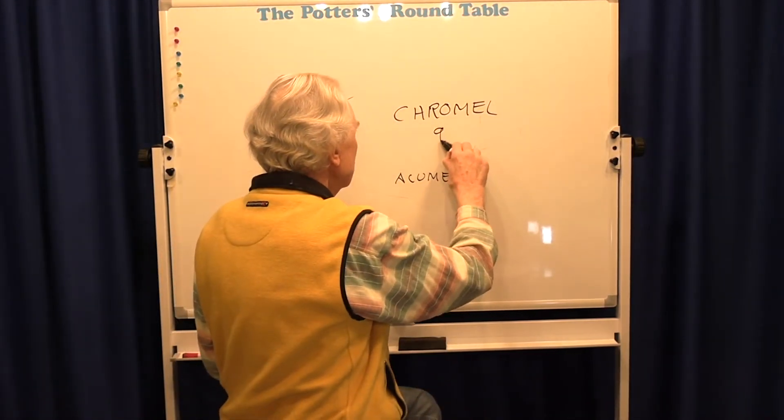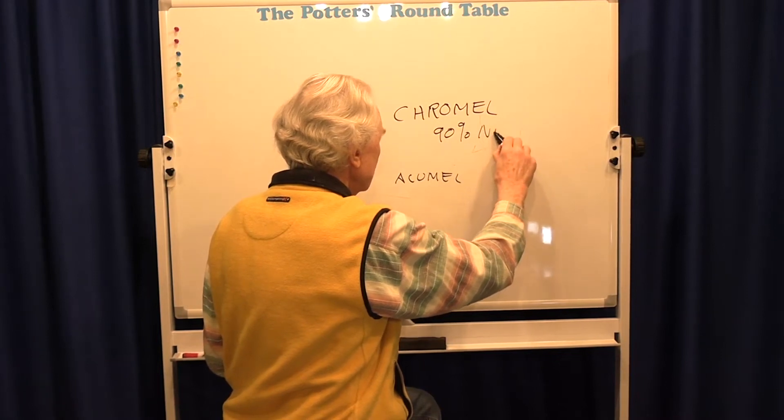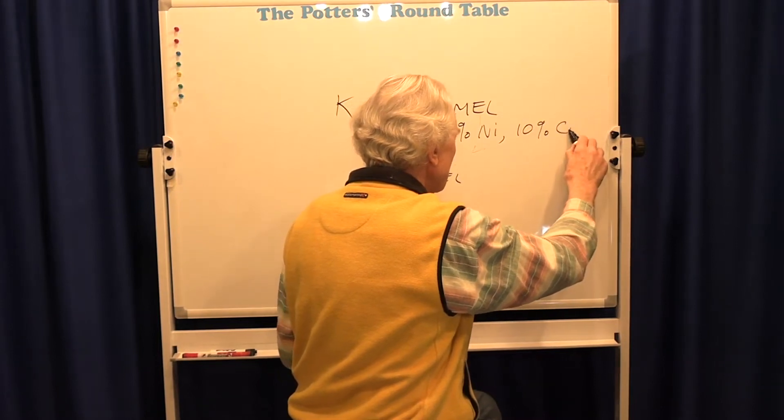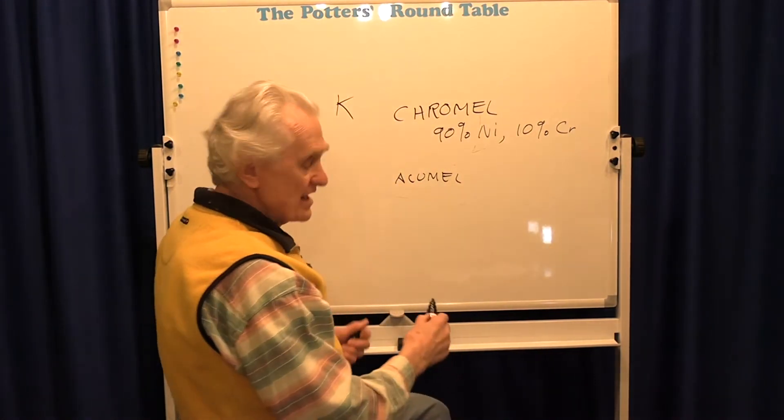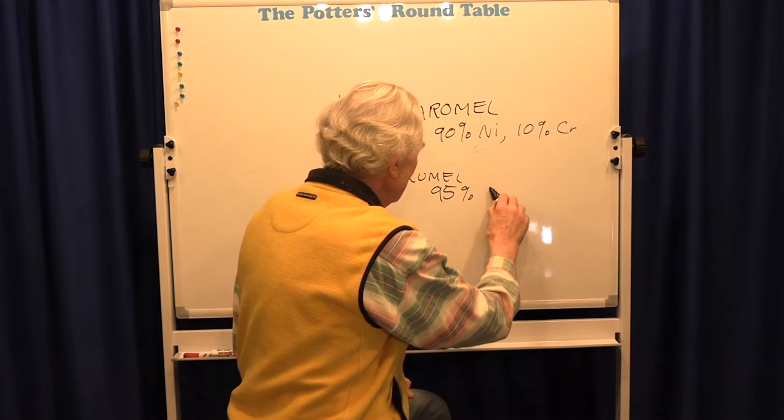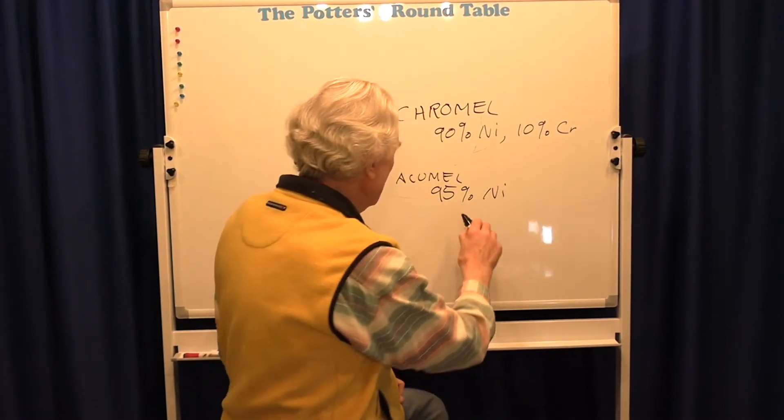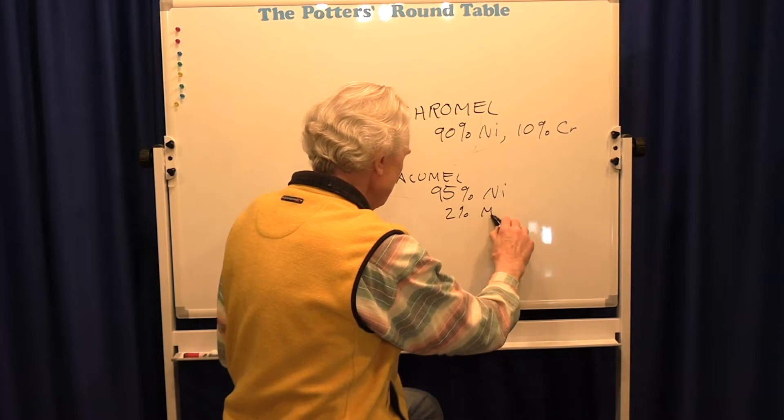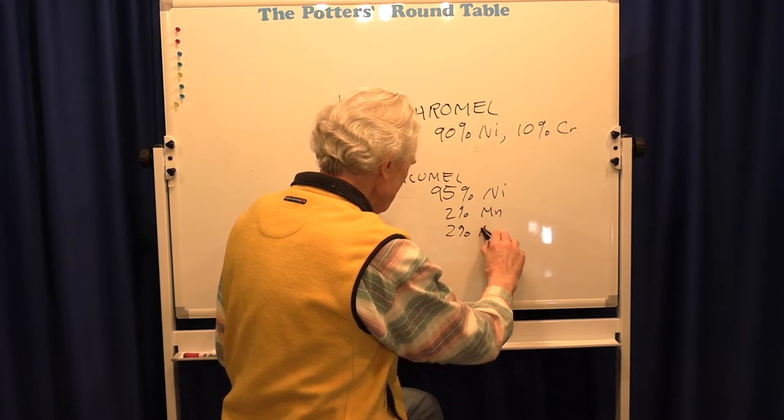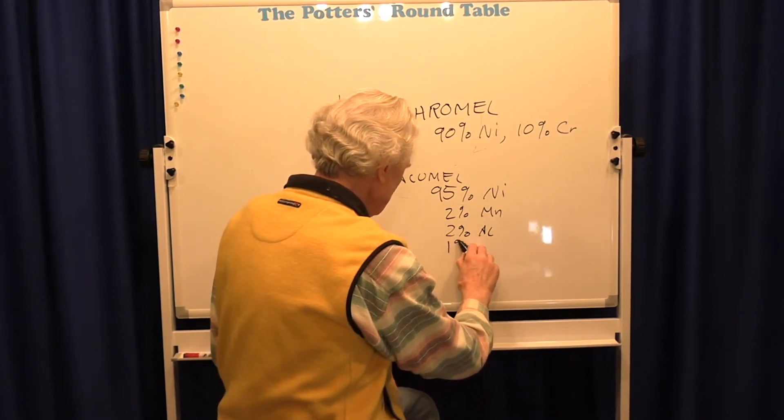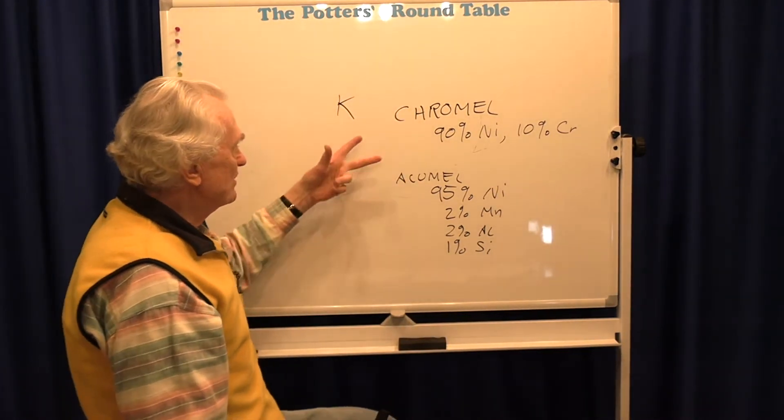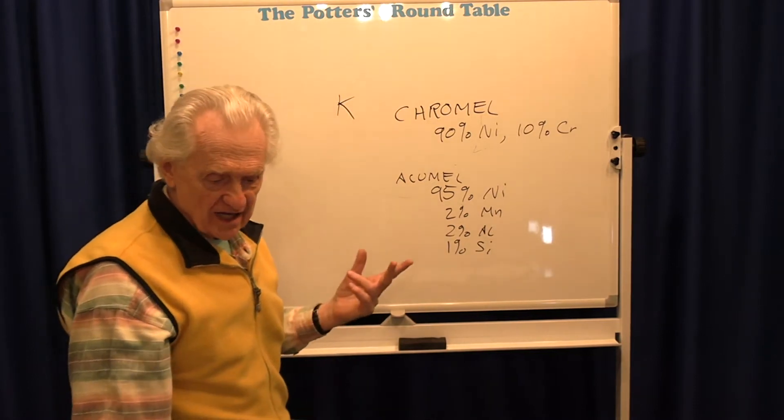The chromel is 90% nickel and 10% chrome—this is chrome, not chromium oxide, because these are metals. And the alumel is 95% nickel and 2% manganese and 2% aluminum and 1% silicon. So even though they both have a lot of nickel in them, they're different enough that when I connect these two wires together, I can produce a voltage.